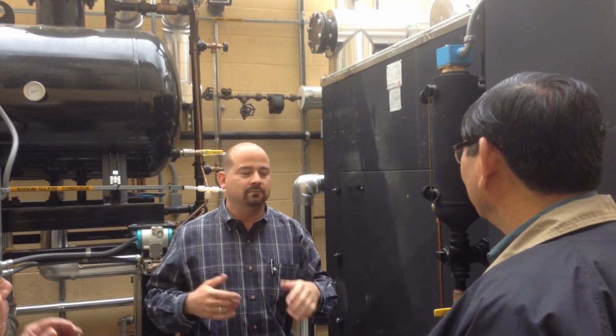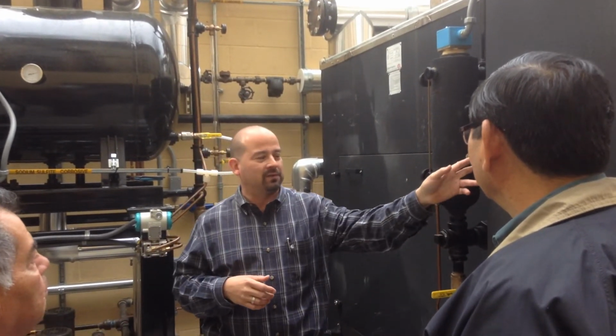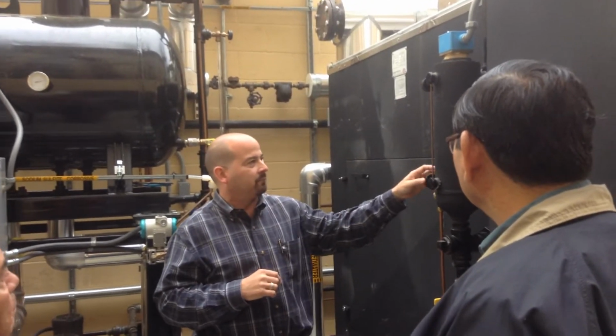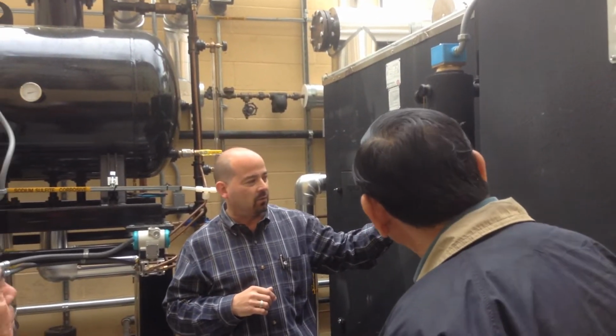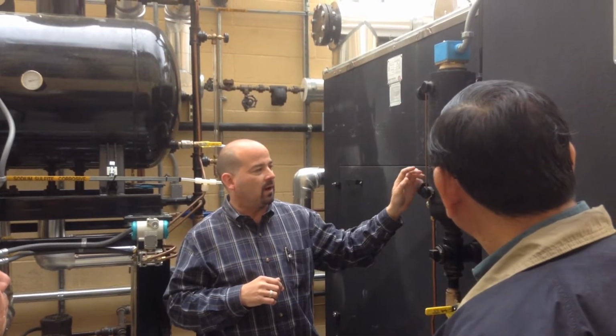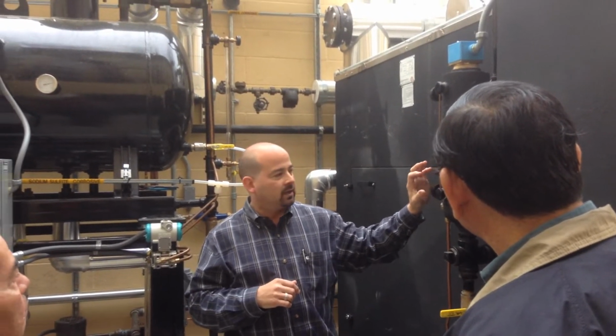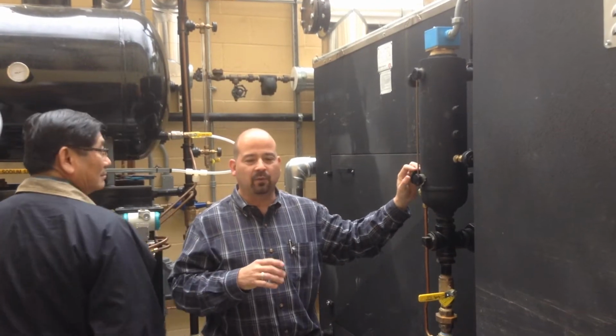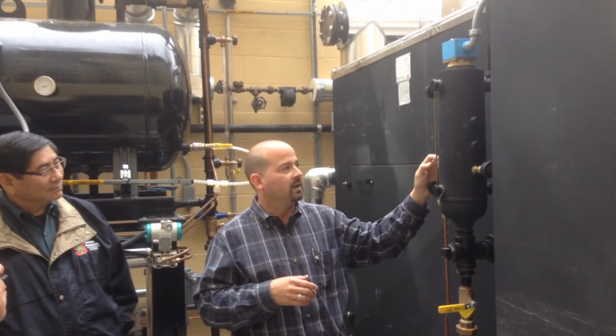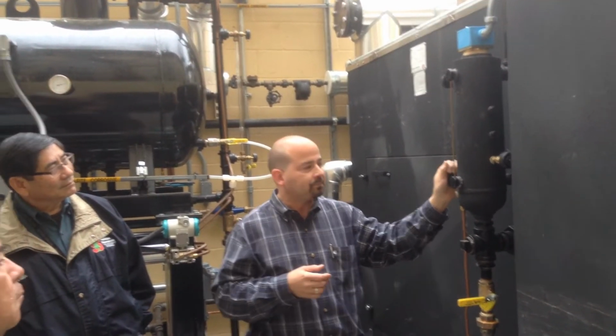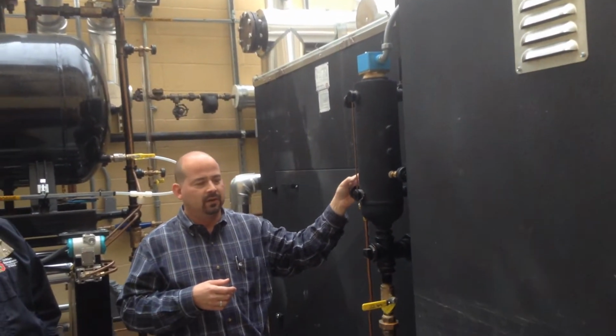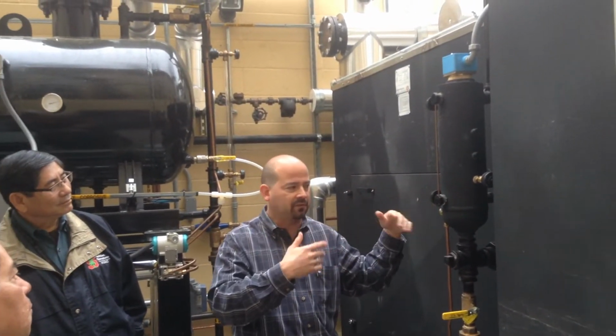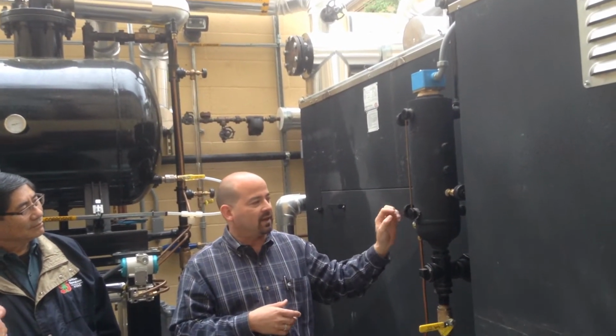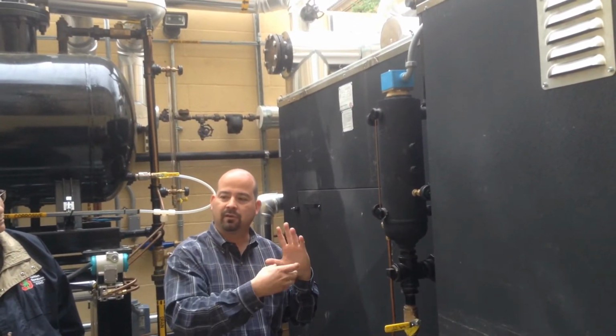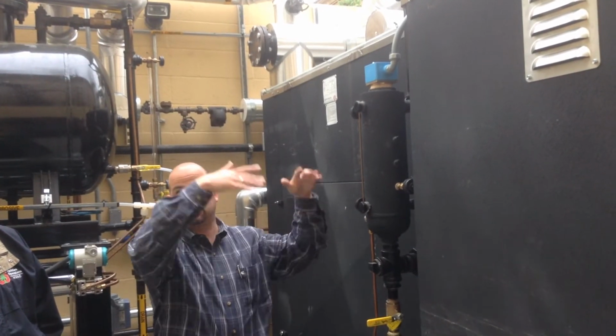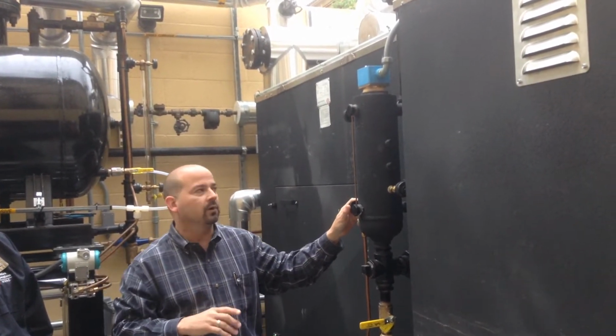That's not really required anymore, but for whatever reason they're requiring just the one, because you have the water glass here that tells you what the water level is. The water glass, the fixture set, this is a 1/2-inch fixture set, and if for whatever reason, and it does happen occasionally, the water glass breaks, a lot of times near the nut here, it'll get etched just from years of service, and then it might break. If it does, there's a little ball check in there, so if there's pressure, the ball check will seat, and it won't let steam just go all over the place. That's the way it's supposed to work.